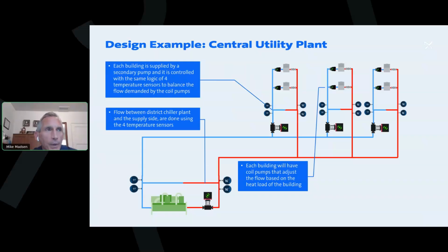I don't. It was probably 15 or more years ago that they invented variable primary. With variable primary, we've got these very high head pumps, and then we've got the control valve burning up that extra head pressure that the pump is producing. Right. So I think if you weren't doing distributed pumping, you're going to get more energy savings from a primary secondary type system, because a primary skid can be smaller, and then the secondary pump is still big and we're still wasting energy. But I think it's actually going to be a little more cost effective.